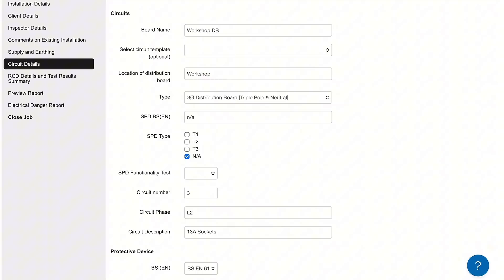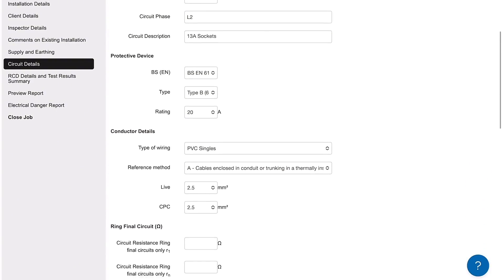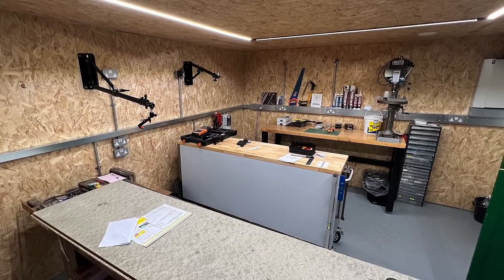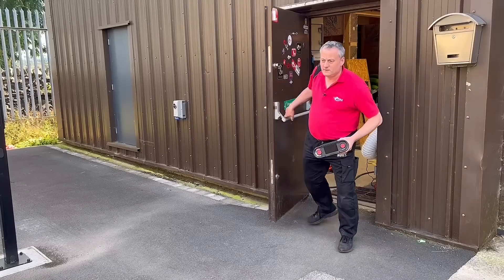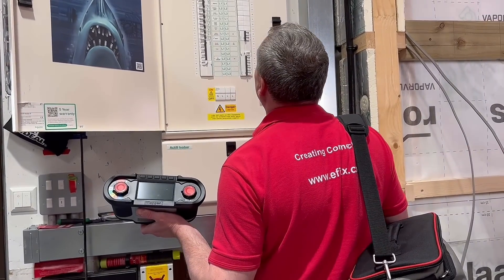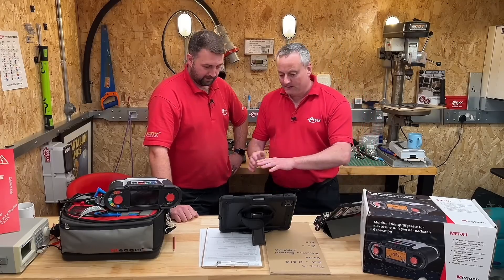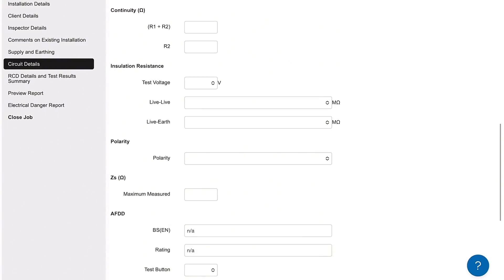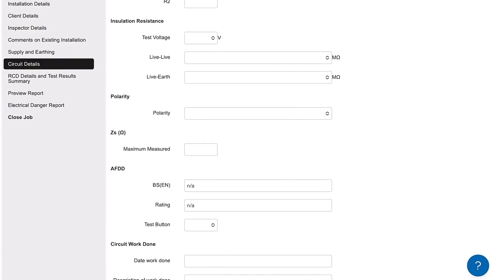As we go next again, all this has been drawn in automatically — I haven't put any of this information in. It's telling you it's from the workshop DB, it's three phase, what it was wired in, the CPC sizes, the fuse — 20 amp breaker, an A3 radial. As electricians, we like carrying out the tests, and we certainly like walking around with the X1 because it looks so snazzy. Once we perform tests on the Megger X1 and tell it to save, it automatically transfers that information onto the app and pre-populates all data, which prevents fat fingers.